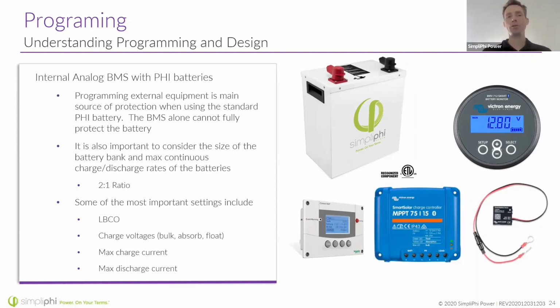The BMS can also open circuit if the inverter is demanding too much current. But as I mentioned, there is no way for the battery management system to turn down the output of current that is there. If a component is demanding or supplying a certain amount of current to a battery, the battery will provide it, right? Unless, designed properly, the inverter is programmed alternatively.